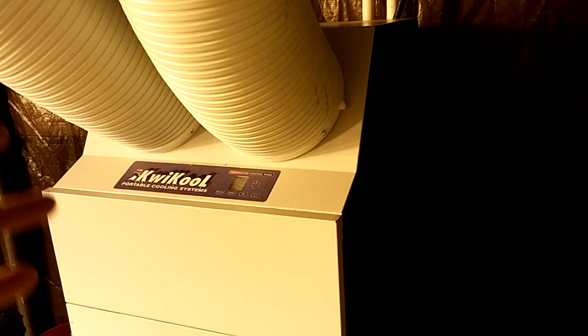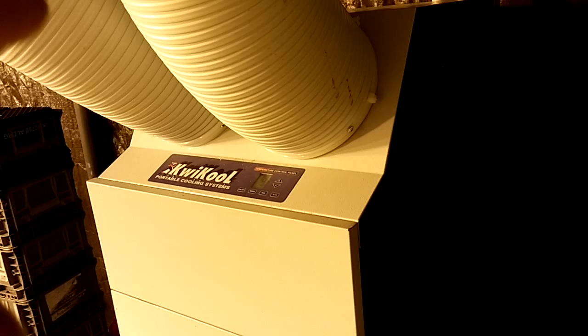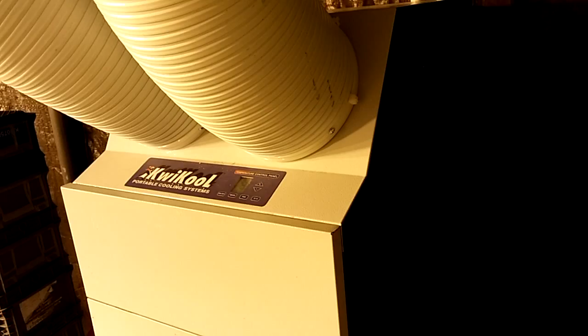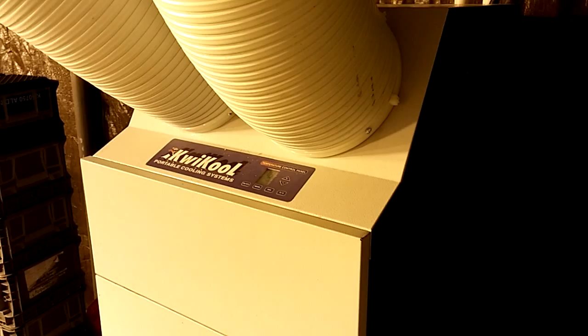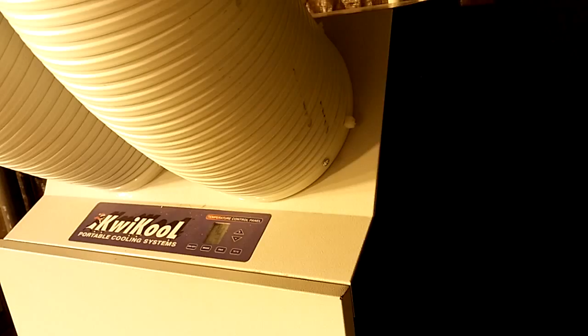The fan blows air across the radiator, cools the water, and sends it back to the AC. This unit has a built-in valve that can automatically adjust the freon and temperature based on the temperature of the water coming in. If your water's at 50 degrees, it opens up for better cooling; if it's at 70 degrees, it restricts and adjusts accordingly. So it can always cool your room down to 72 degrees minimum based on whatever water is coming in.